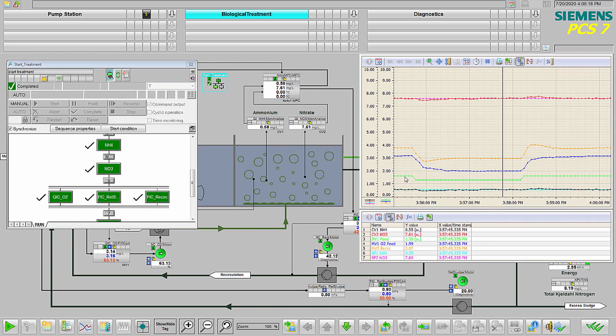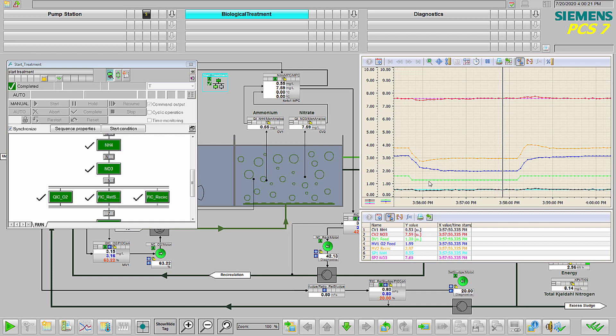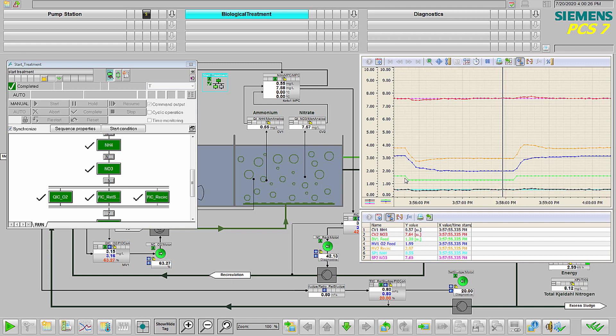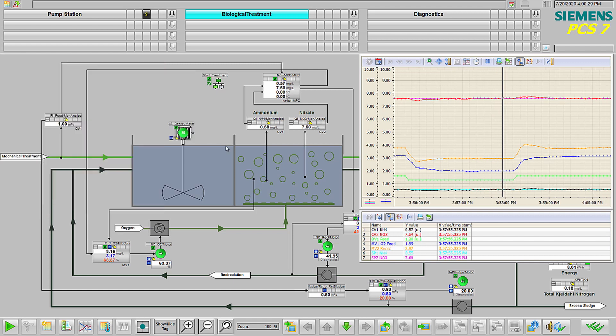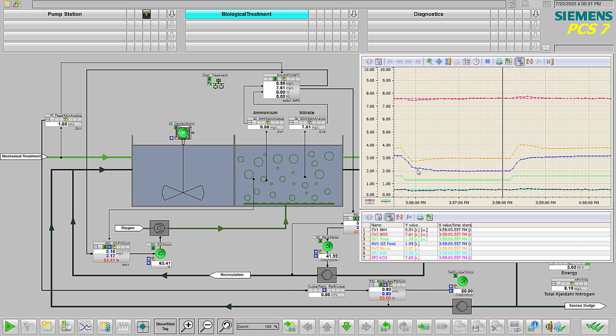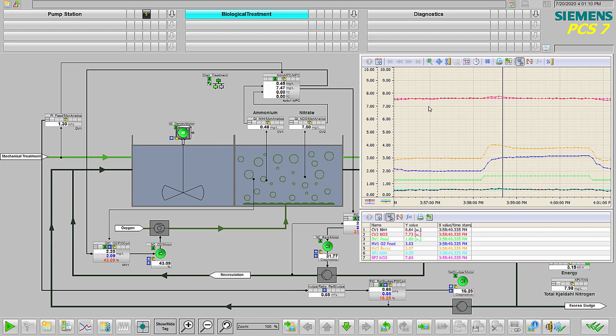So, with an MPC algorithm running in a wastewater treatment plant controller, the control system maintains tight control of the process, even during uncontrolled swings in the feed rate. When a fluctuation is detected, the MPC smoothly adjusts the oxygen blower and sludge pump to maintain the nitrate and ammonium values close to their set points, without too much oscillation.